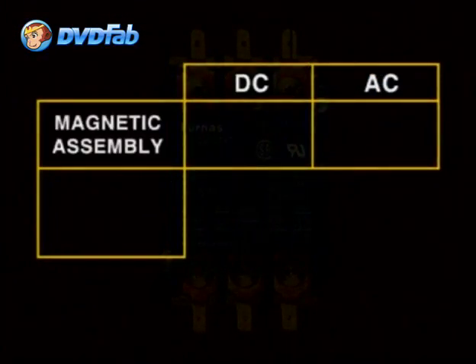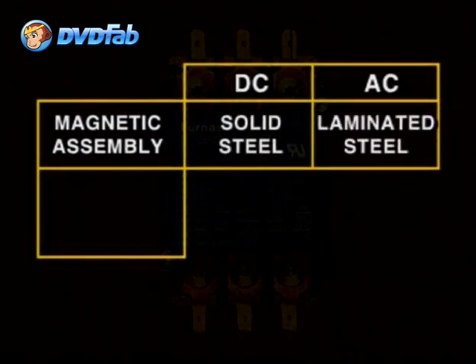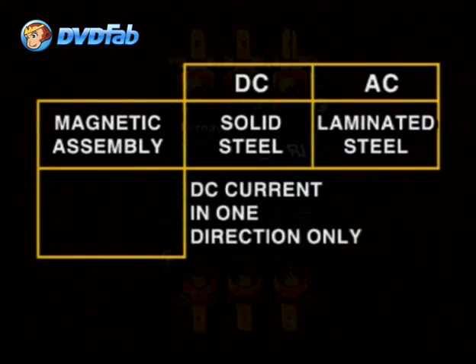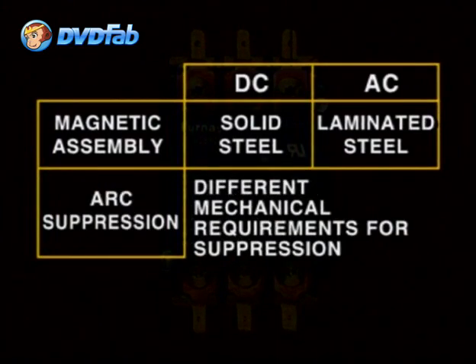The magnetic or coil assembly of a DC contactor is made of solid steel instead of laminated steel, as in the case of the AC contactor. The reason being that DC current only flows in one direction continuously and doesn't create eddy current problems. The other major differences are the electrical and mechanical requirements to suppress the arcing created during the opening and closing of the contacts. We'll touch on this subject next.